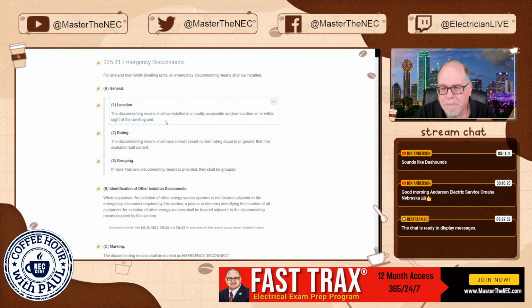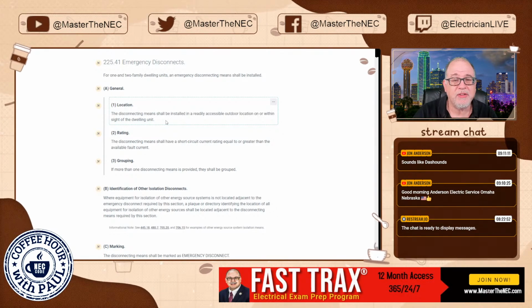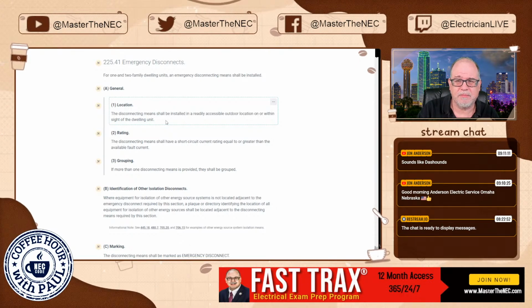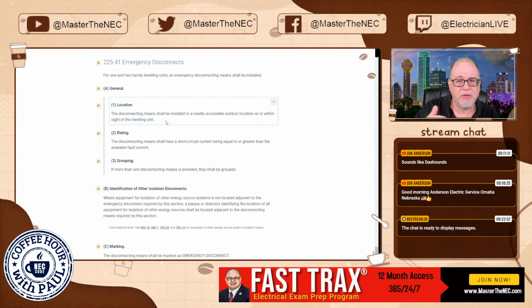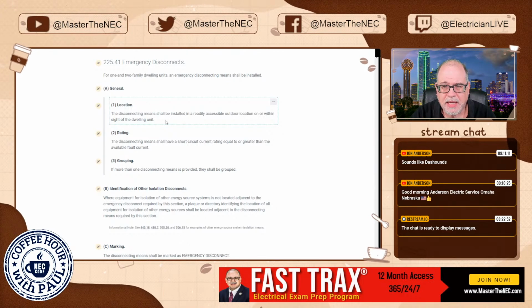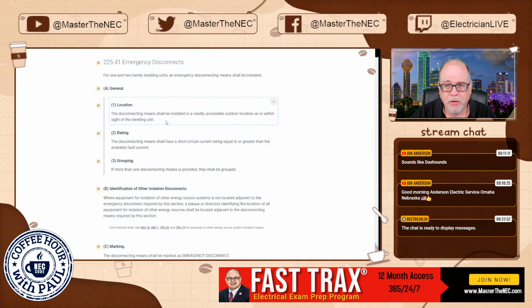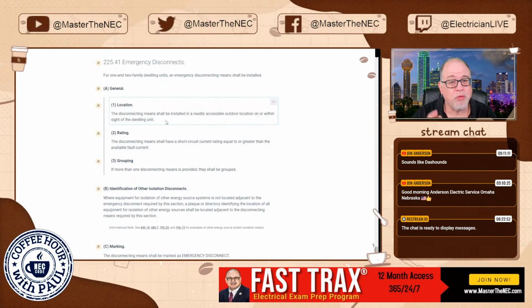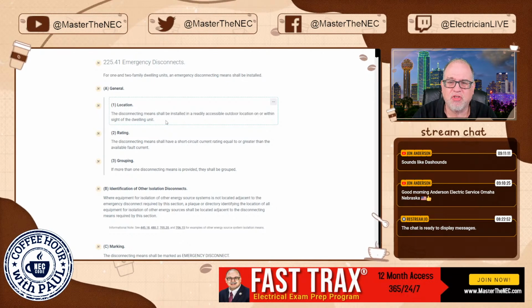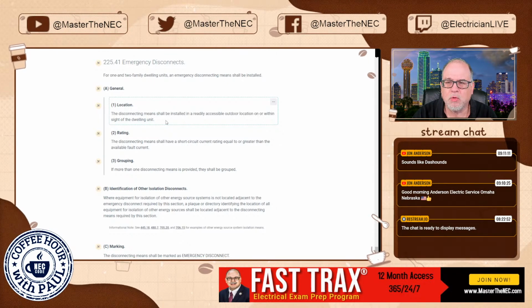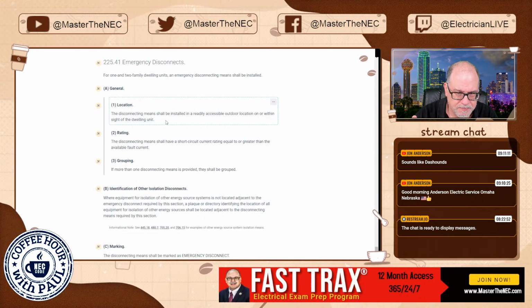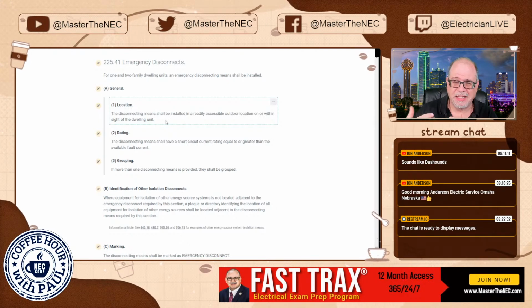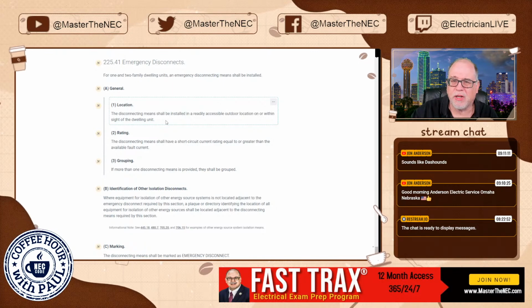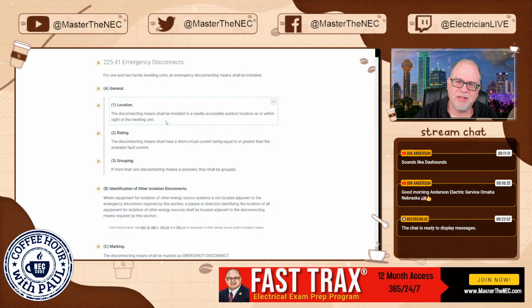But anyway. All right. So this new disconnect, this emergency disconnect that applies to 1 and 2 families that are fed by a feeder can be where? On or within sight of the dwelling unit. The rating, the disconnect means shall have a short circuit current rating equal to or greater than the available fault current. Okay, so we're going to have to know what that available fault current is. Usually 1 and 2 families are going to be limited to 10,000 amps anyway.